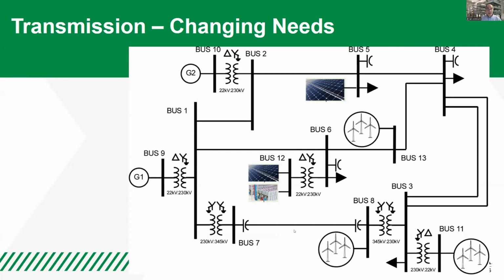These systems are coming in, many put in by third-party groups funded by venture capitalists. This has increased requirements on how interconnection agreements are set up, to maintain resilience in the transmission system. Previously, these systems had a hair trigger and would shut off if almost anything happened in the power system; now they have to stay on for a certain length of time.